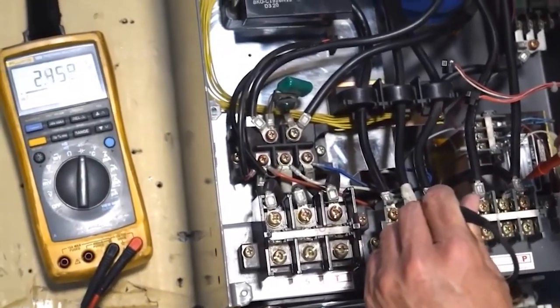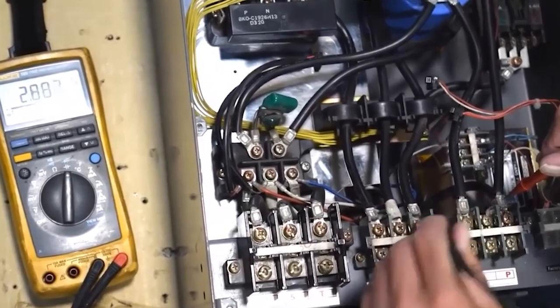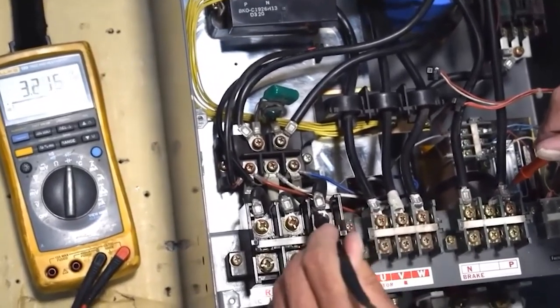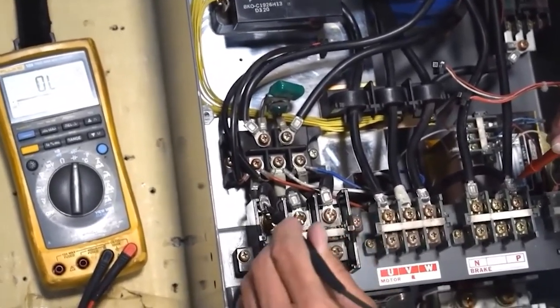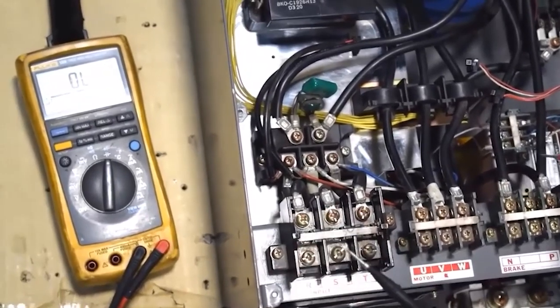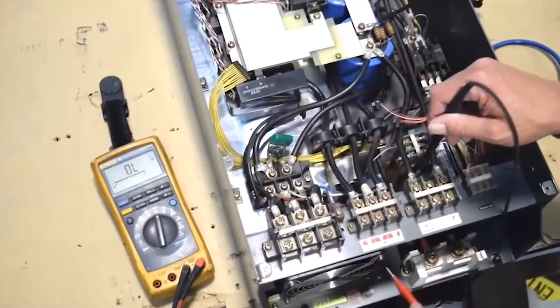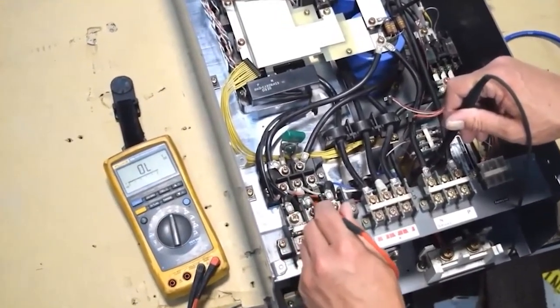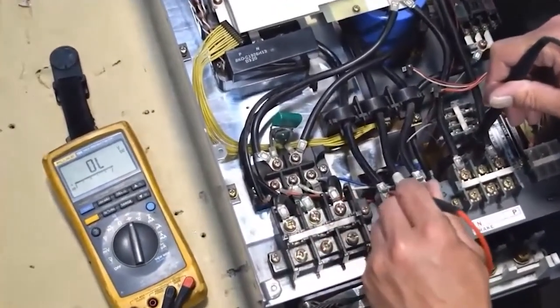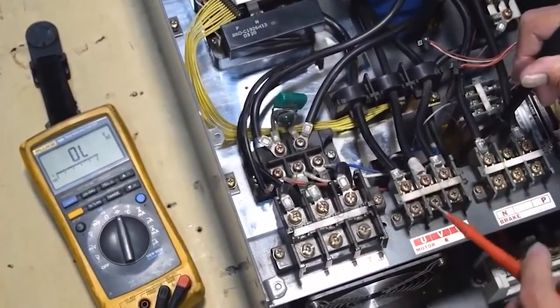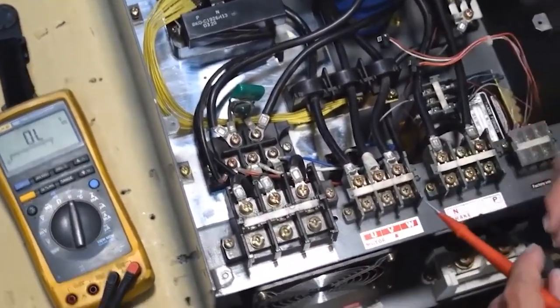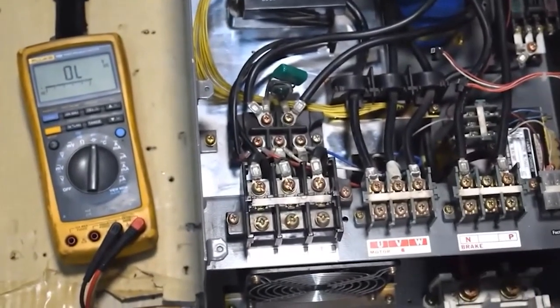So now I'm doing a test that just shows it charging. I put my positive lead on my positive bus and started measuring across. You notice my meter started low, then it charged up till it got to an OL. And that's what I'm looking for. If it doesn't charge up, then that's an indicator that I've got an open on my DC bus somewhere. Maybe some fusing, maybe the pre-charge circuit's opened up. Something on the DC bus is not healthy.